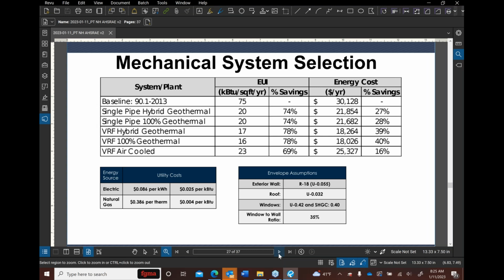If you look on the right-hand side, the energy cost difference between the air-cooled and the water-cooled is give or take $7,000 per year. If the geothermal field would have cost in excess of $300,000, you could see the payback on that would have been a very long time.